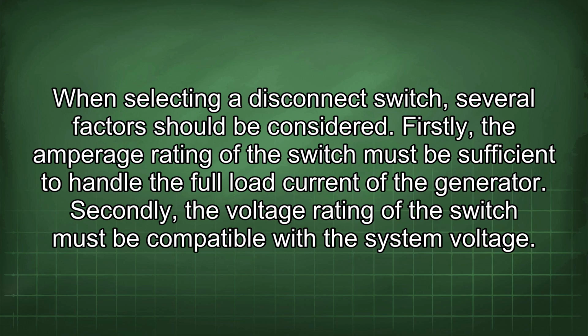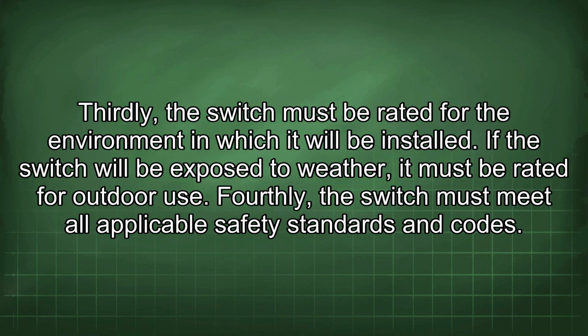When selecting a disconnect switch, several factors should be considered. Firstly, the amperage rating of the switch must be sufficient to handle the full load current of the generator. Secondly, the voltage rating of the switch must be compatible with the system voltage. Thirdly, the switch must be rated for the environment in which it will be installed. If the switch will be exposed to weather, it must be rated for outdoor use.